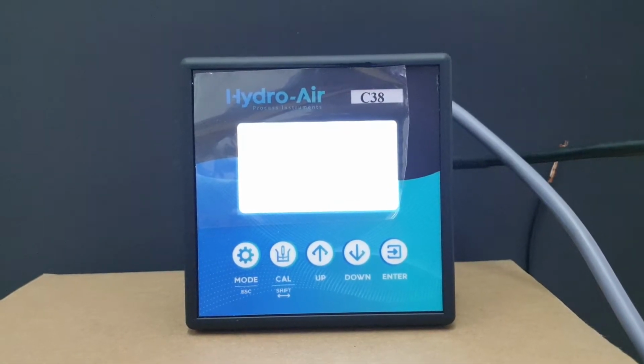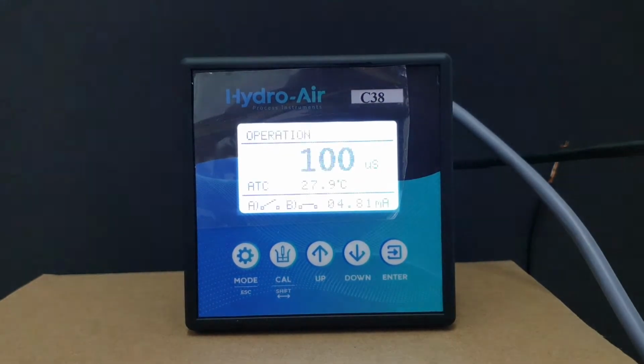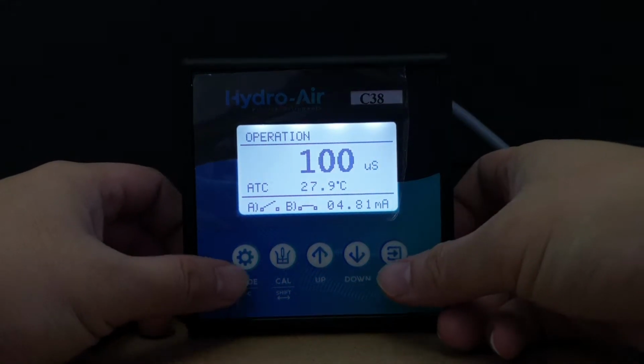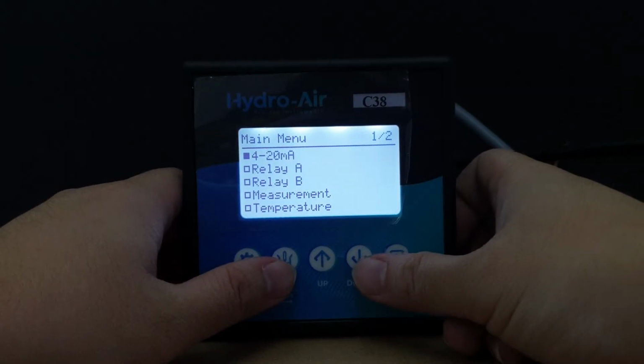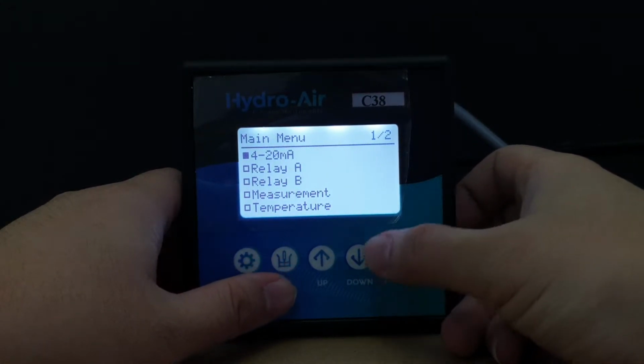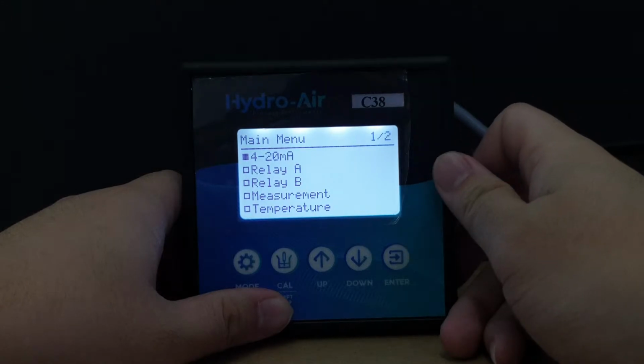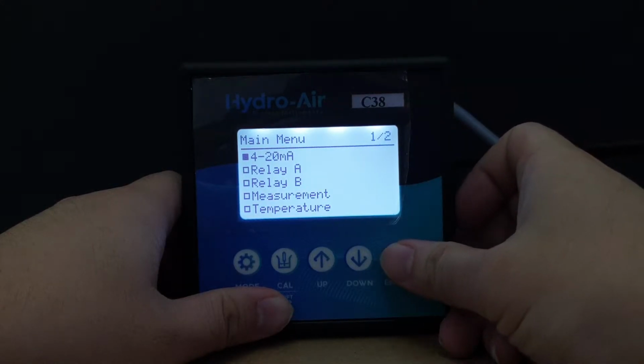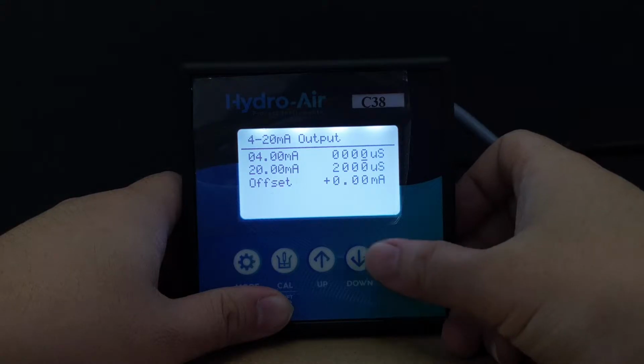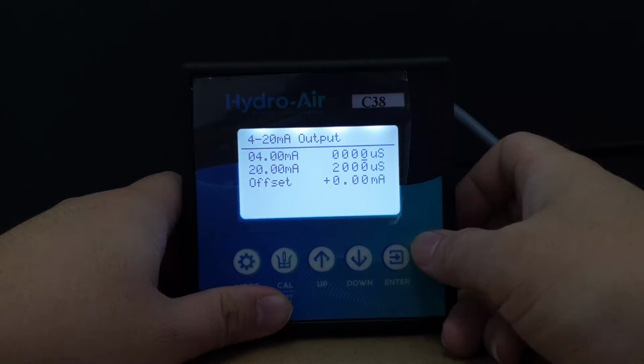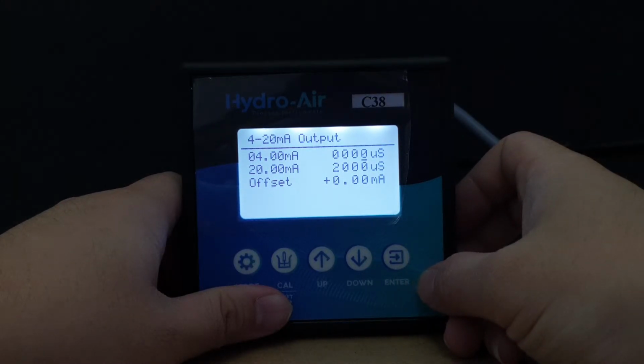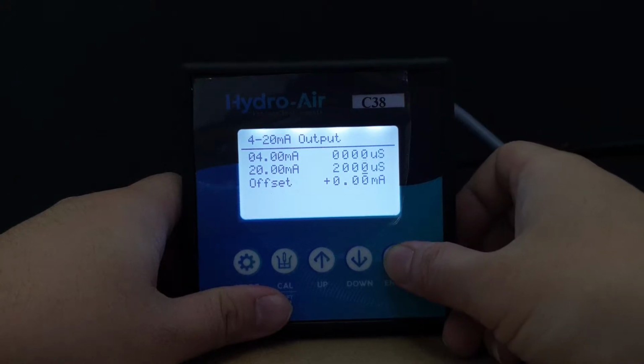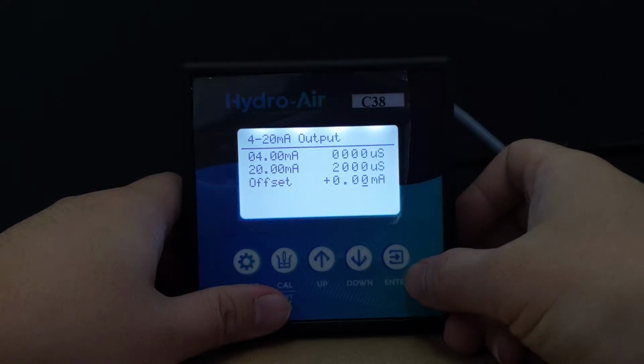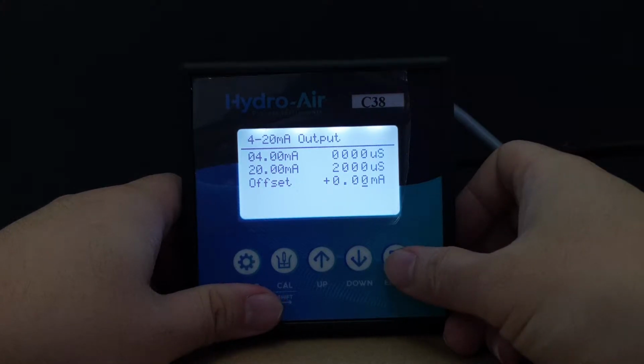In today's video, I'll be demonstrating how you can perform configuration on your Hydro-Air C38. Let's get started. First off, press mode once and you'll be at the main menu. From this list, we're able to tell that the C38 has one current output with two relays. The 4 to 20 mA output setting allows you to configure the scale for the 4 to 20 mA current output. It comes together with an offset function to enable soft tweaking.